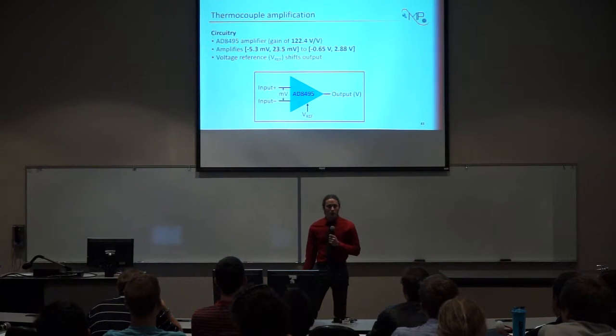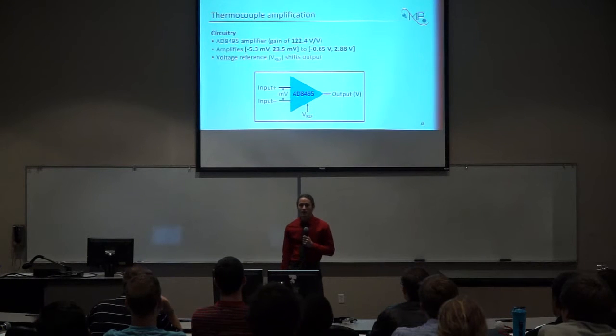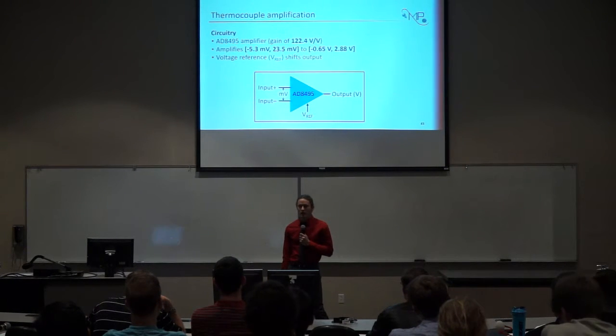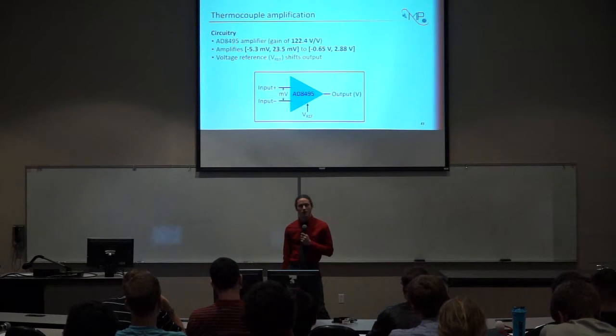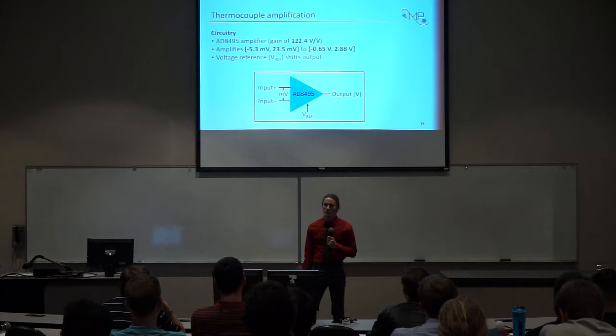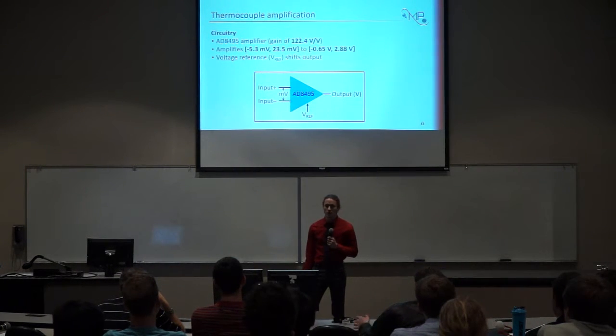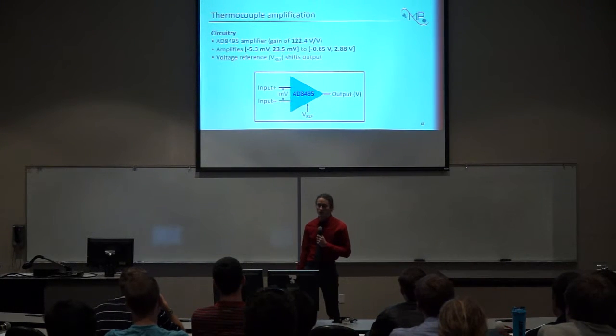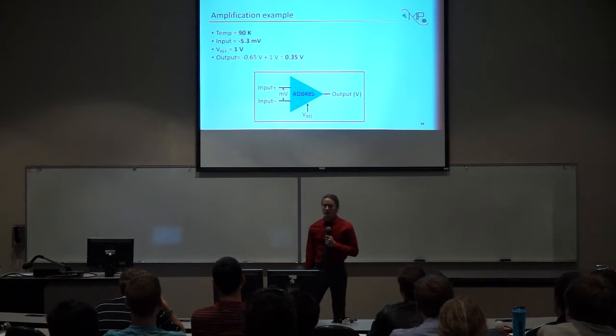For the amplification of the thermocouple, we already have the circuitry designed and fabricated. We're using the AD8495 amplifier, which is an instrumentation amplifier specifically made for type K thermocouples, but also works for type T. And for that, it has a 122.4 gain, which gives us negative 0.65 volts up to 2.88 volts on the output. It has a voltage reference in order to shift that negative voltage up so that we can get it to the ranges that we expect we're using for our data acquisition system. Just for an example, for the 90 degrees Kelvin, that will have a negative voltage. We can use a 1 volt V reference to push that up to 0.35 volts, so then it'll be an acceptable range for our system.